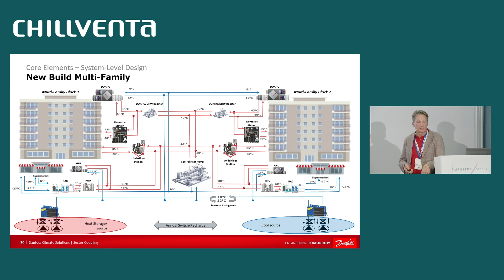So we can recover all the heat from the cooling we're supplying to these multifamily facilities and store it in that aquathermal energy storage system, to use later to increase the efficiency of the heat pump that's boosting it up to supply that heat.